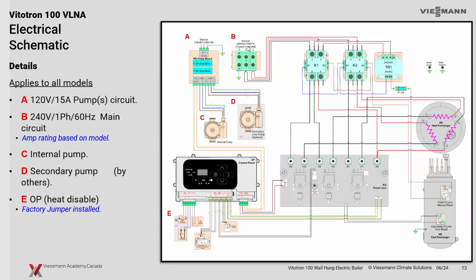So there's the 120 volt. And then on the contactor side here, we've got our L1, L2. That's our 240 volt coming in. And that's going to come over and go through some contactors. And then on the actual operational side here, we've got a step down transformer. And your limits are actually wired through a 24 volt circuit here, and they provide power for the operating limit here for the triacs to operate your elements to start and stop those. So if the operating limit opens, it kills power to this board where the triacs sit, and of course your elements are not going to get powered up there.